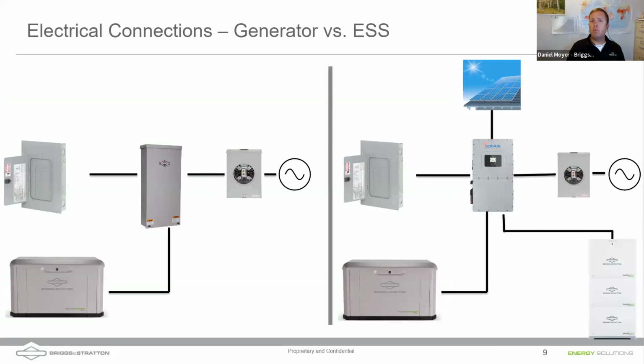So to level set us, what does a generator system typically look like? On the left is essentially what you'd see: you have the grid, a meter can, and there should be a service disconnect. You go into a transfer switch, and during a grid-up situation, all that power is flowing right into your load center. When the grid goes down, the generator automatically detects the loss of grid, starts itself up, then sends a signal to transfer the transfer switch. Now the generator's power is feeding through the transfer switch into the load center. That's crucial—we need the transfer switch because the last thing we want is backfeeding the grid with our generator power, potentially putting linemen down the road trying to restore power into the neighborhood in danger.